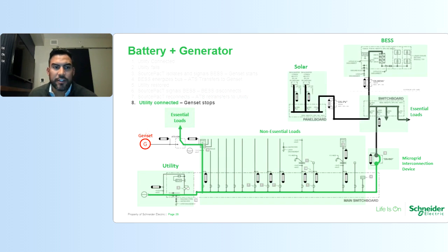Now, once that microgrid interconnection device closes, the energy storage system should come online again in a grid interactive mode. As you can see there, that critical panel board, the solar system, and the energy storage system are now operating in the grid interactive or grid connected mode again. And now your system is in normal operation. So this is one design on how generator and battery operate together.